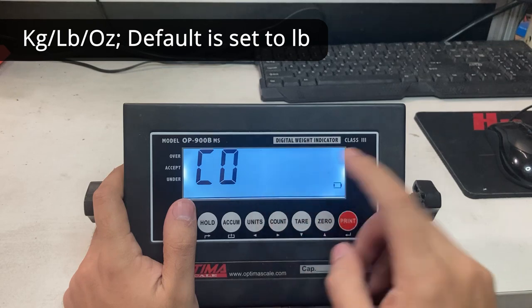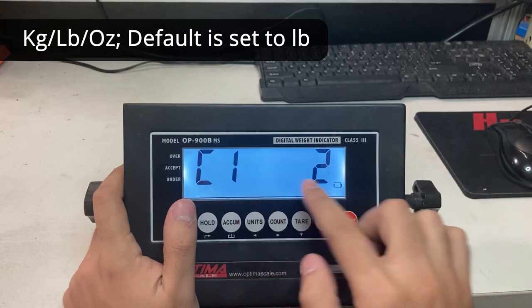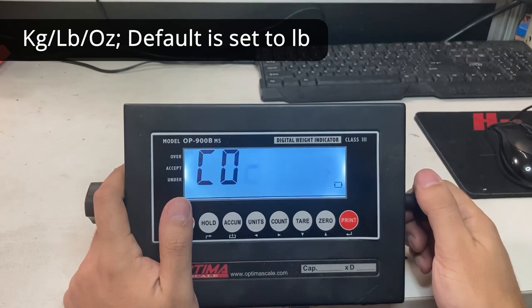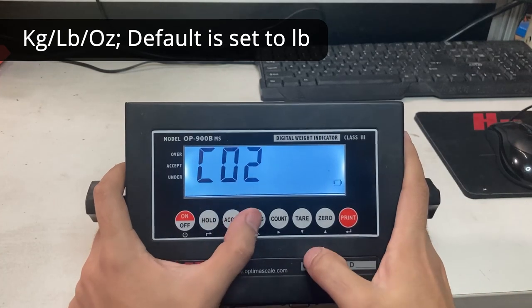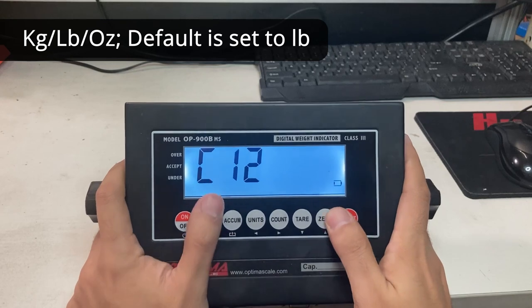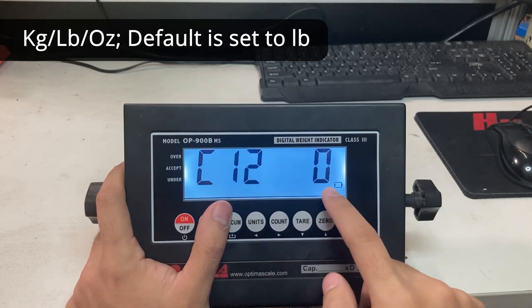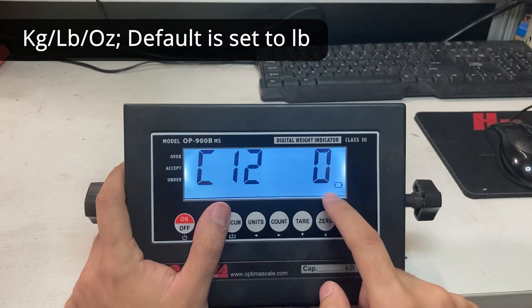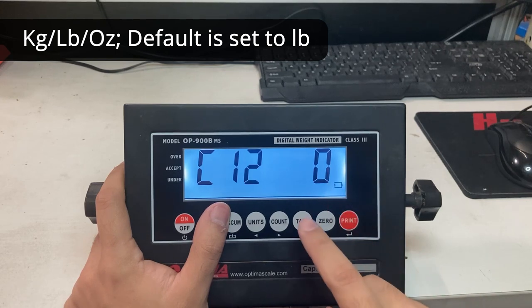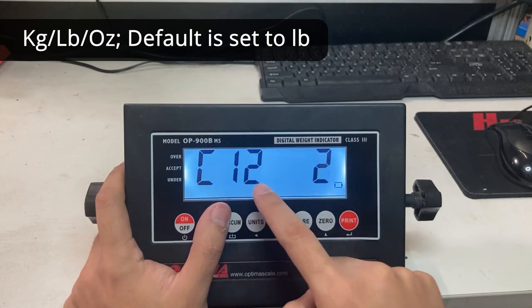What I could do is set C01 to 2. You can push up and down. And then we have to go to C12, so I move left, press the units button, and make that 1. So C12, and right now it's set to 0. What we're going to do is set this to 2. C12, 2.